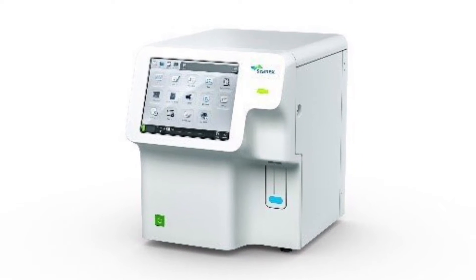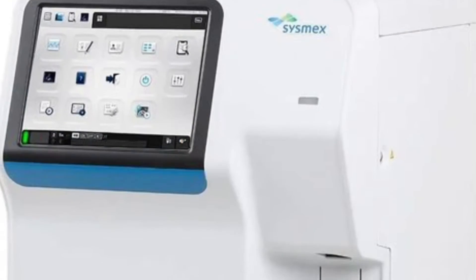They have changed the appearance of the machine slightly. It is a very compact model and weighs only about 25 to 30 kg. It is a completely white machine with a good LCD monitor. It measures approximately 20 parameters and has three histograms. Importantly for laboratory technologists, it has 20 flagging systems — compared to other hematology analyzer models from any company, 20 flagging systems is very good. The sample volume needed for the XQ320 is only approximately 16 microliters per test.